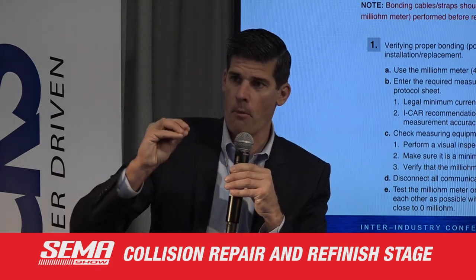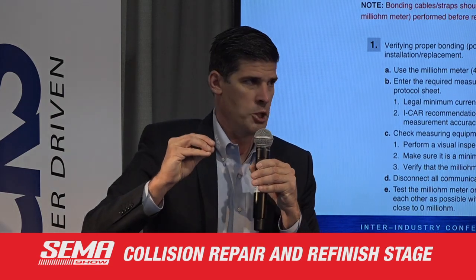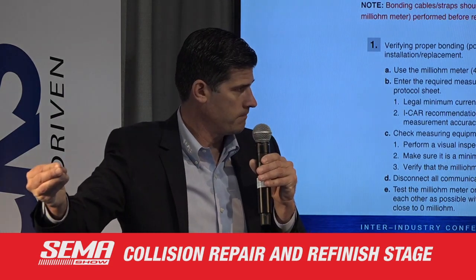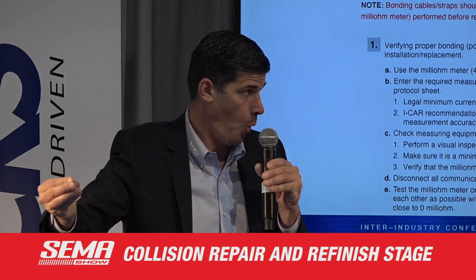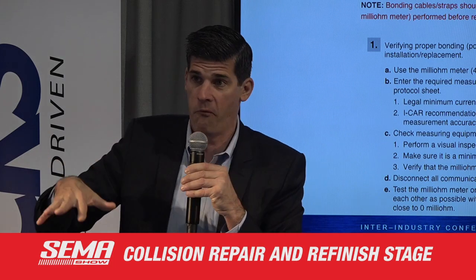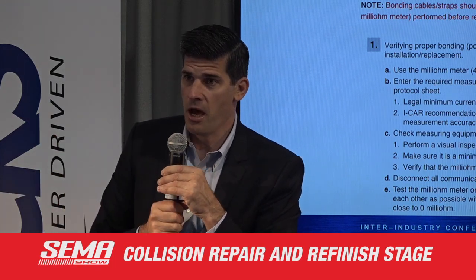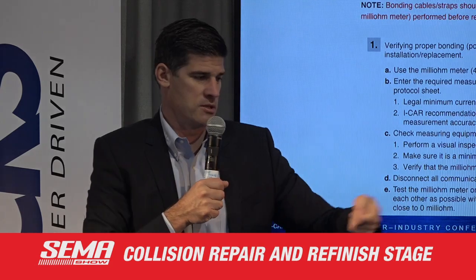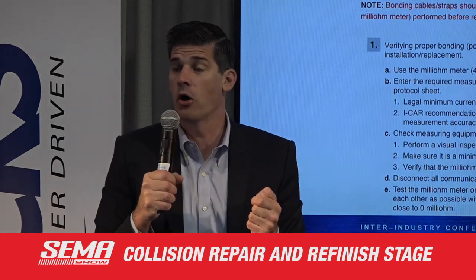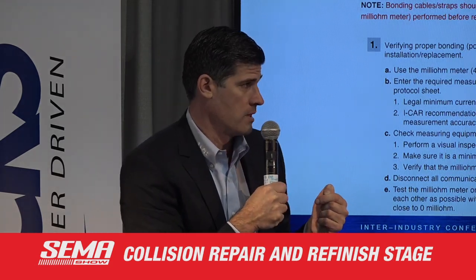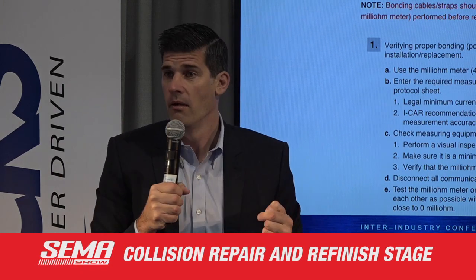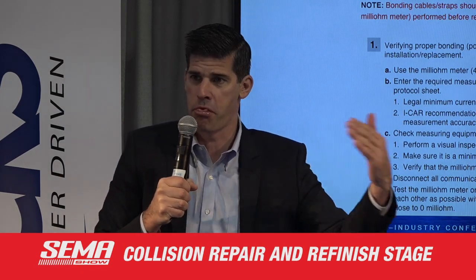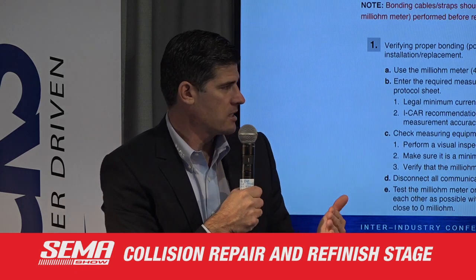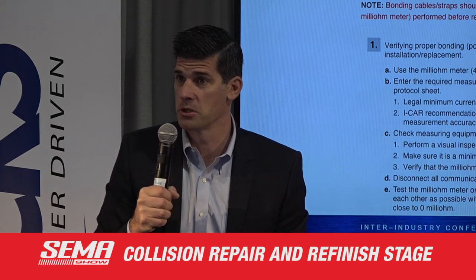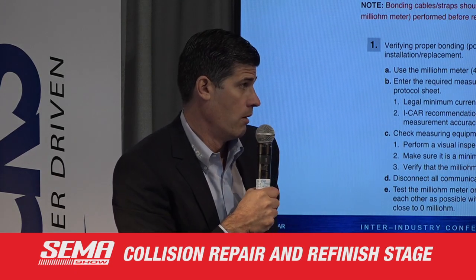But when this component is not bonded properly, we're talking about milliohms here, and this is a new learning curve for our industry. We're used to 5 ohm cables, measuring that, it's nice. Now we talk about thousands of an ohm. 1 milliohm, for example, for 1 meter or 3 feet of cable, is an appropriate measurement. So we're going lower than a milliohm.